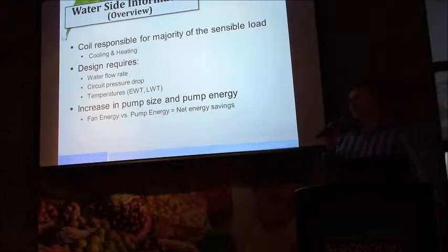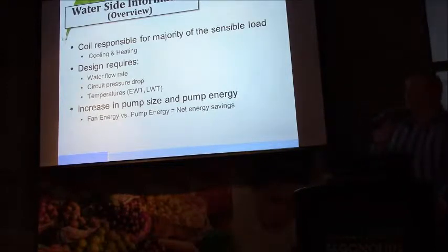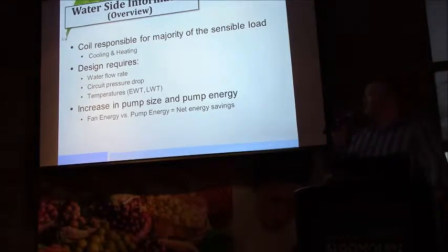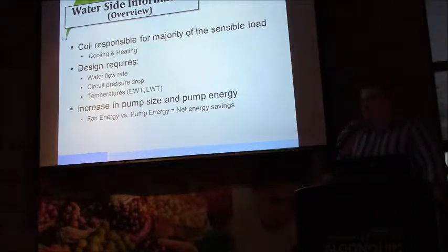And your entering water temperature, again, is governed by your psychrometric calculations that you do at the beginning to ensure that we're above the dew point. And on that note, it is possible to run the chilled water at the dew point of the space, but it's not recommended. Generally, a good rule of thumb is to have the chilled water at least 1 degree Fahrenheit warmer than the dew point of the space. The warmer the water we make, the greater the safety factor there is, obviously.